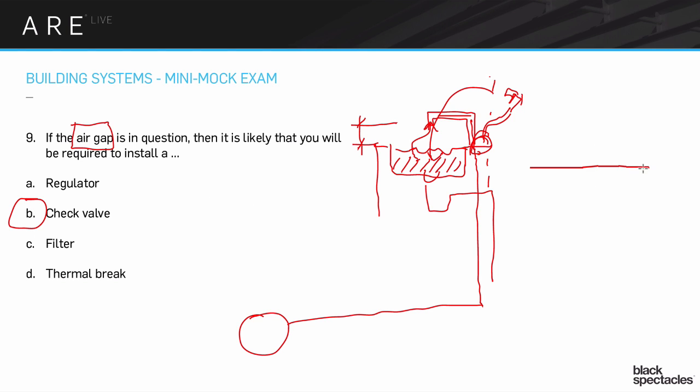So a check valve is somewhere in that pipe. It's going to be a little device, and that device is going to be set up a little swinging door if you will. And when the water is going this way, that water goes right on through. But if for some reason there's suction and it starts pulling the water the other direction - and that actually happens fairly regularly - imagine that a fire truck pulls up next door to your building and there's a house on fire down the block and they're pumping all this water out of the fire hydrant.